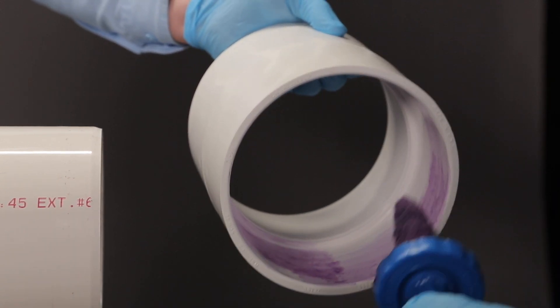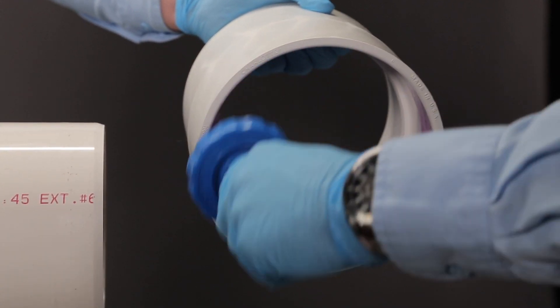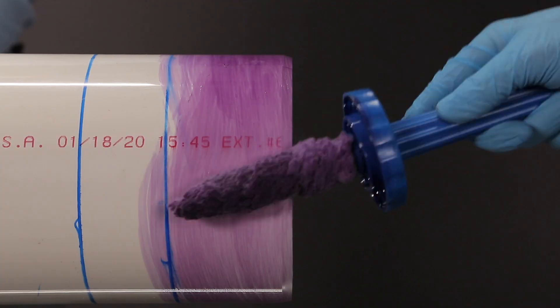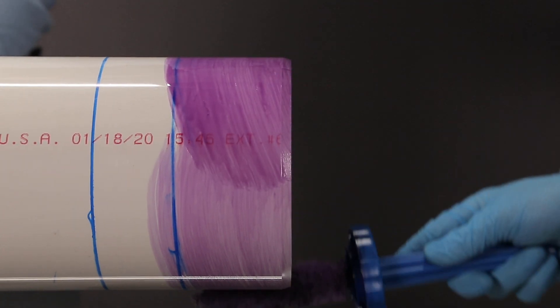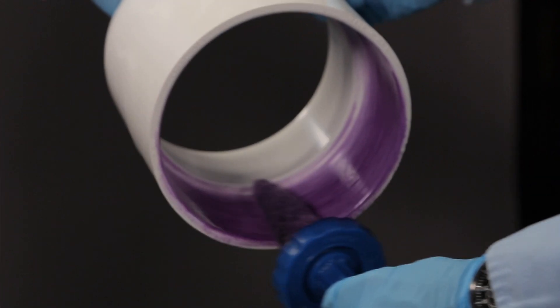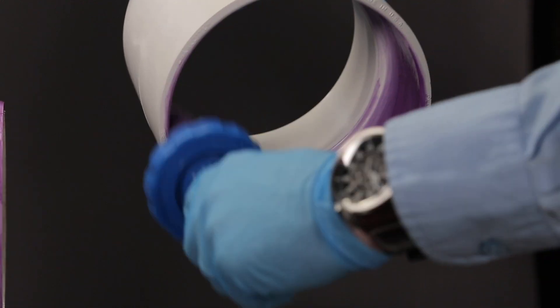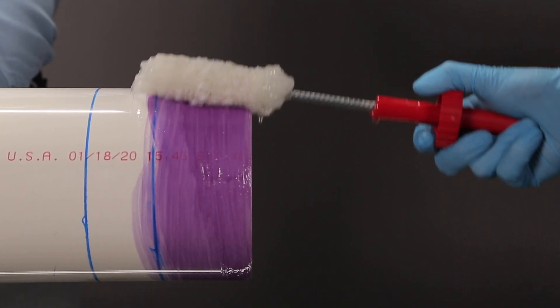For PVC and CPVC of all sizes, first apply primer to the fitting, then to the pipe, then apply a second coat of primer to the fitting. Really work it in aggressively to work the primer into the surface.